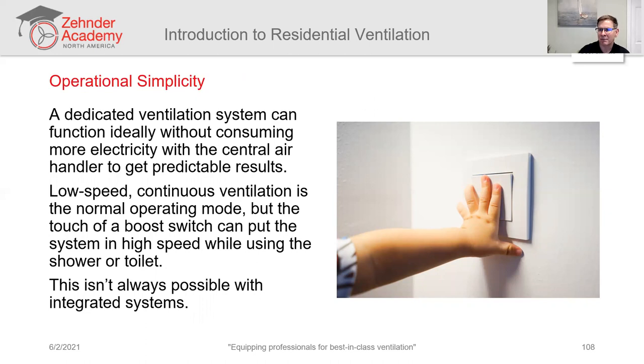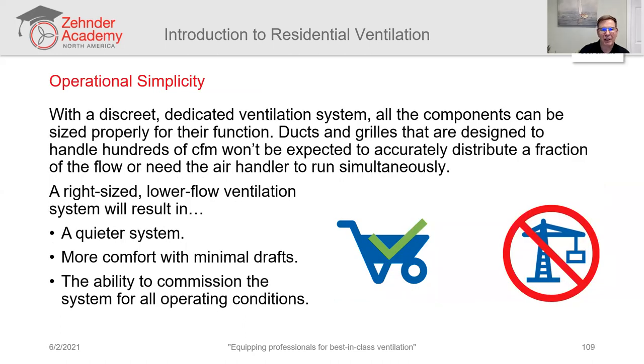Operational simplicity. You can hit the boost system in the bathroom, and you can't really do that as readily if you're trying to do an integrated system. So there are just some operational features that are more valuable when you do a standalone ventilation system. So basically, we're looking at right sizing the system. Don't bring a crane when a wheelbarrow will do the trick. So don't try to involve the whole house heating and cooling system when a smaller standalone ventilation system will do the trick. It'll be quieter. It'll be more comfortable. There'll be minimum drafts. There'll be better air quality overall in places that matter. And you'll be better prepared to commission the system for all operating conditions.